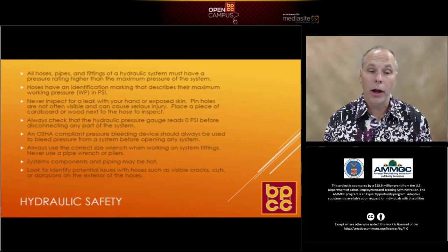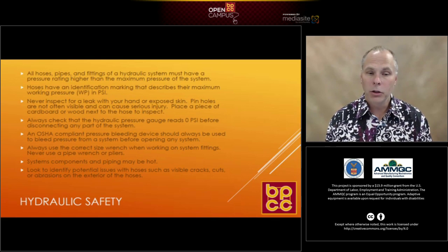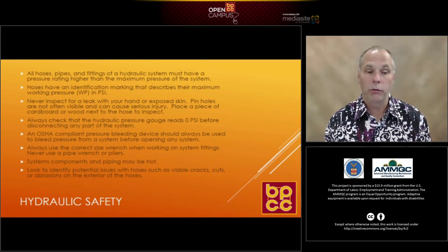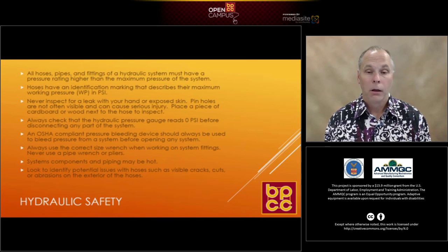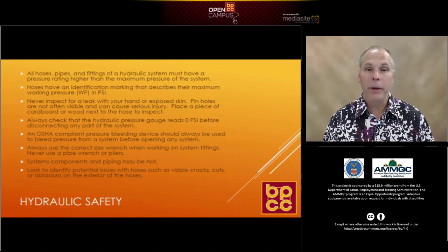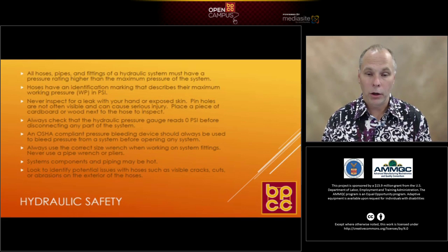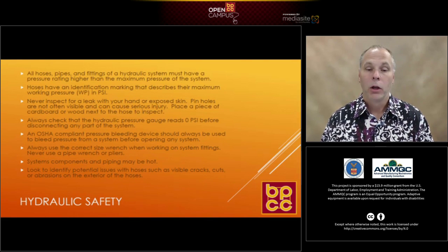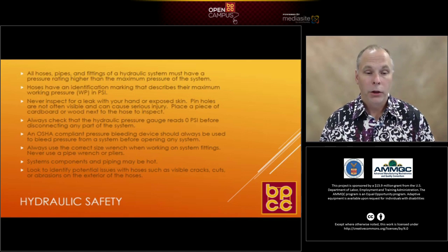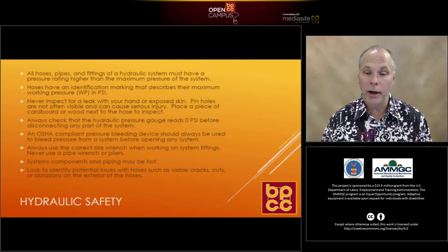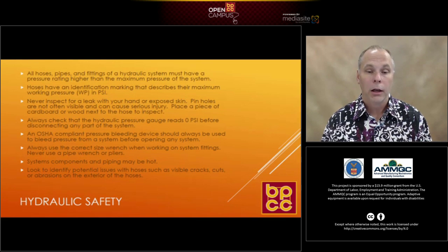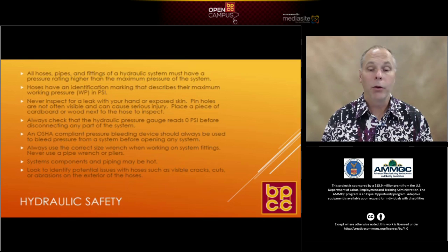Pinholes are not often visible and can cause serious injuries — use a piece of wood or cardboard and place it near the area while looking for leaks. Always check that hydraulic pressure reads zero before disconnecting any part. Even 5 PSI is a lot of pressure for a worker to be around. There are OSHA-compliant pressure bleeding devices; if you're working on a hydraulic system, you should know where those are located.